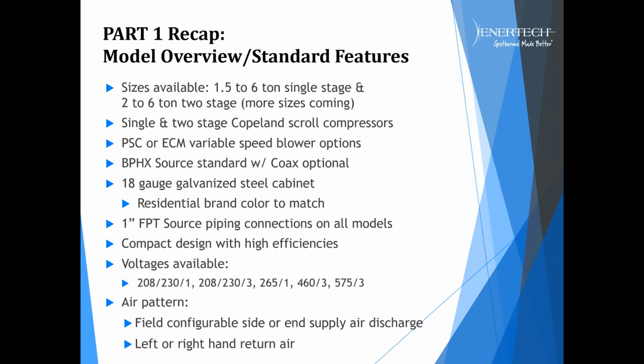Again, this has single and 2-stage Copeland scroll compressors. We have PSC blower motor standard on the single stage, ECM standard on the 2-stage, as well as ECM available in the single stage. We also have some other options with high static and constant torque motors. One thing we're really going to cover today is the brazed plate heat exchanger on the source side of the product. We're going to talk about that in a lot more detail. We also offer a coaxial heat exchanger option for those applications where a coax is a better choice than the brazed plate, maybe residentially with an open loop or commercially with an open cooling tower.